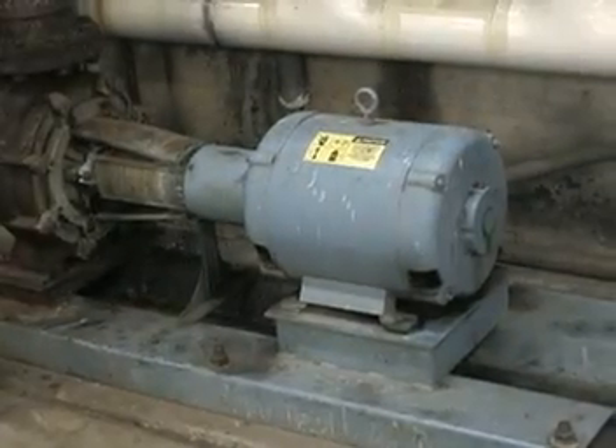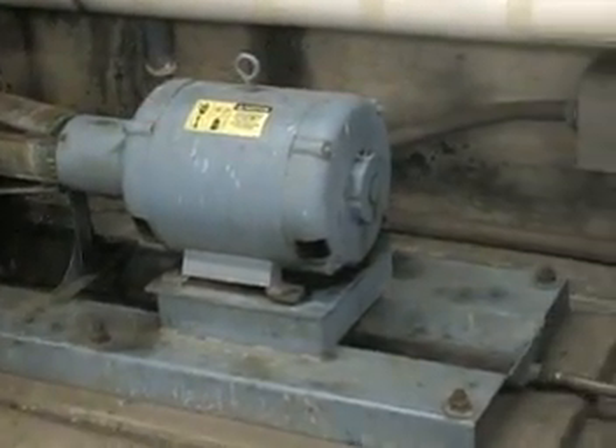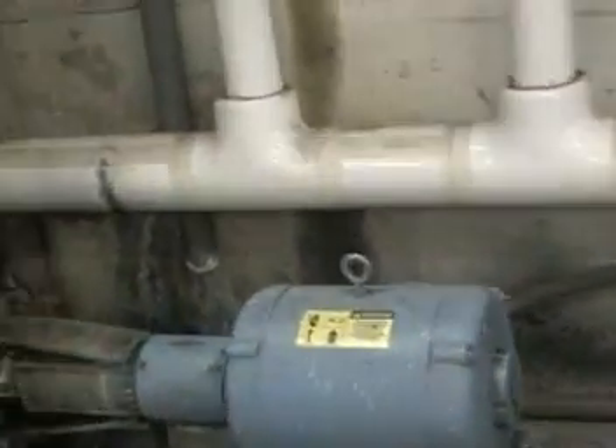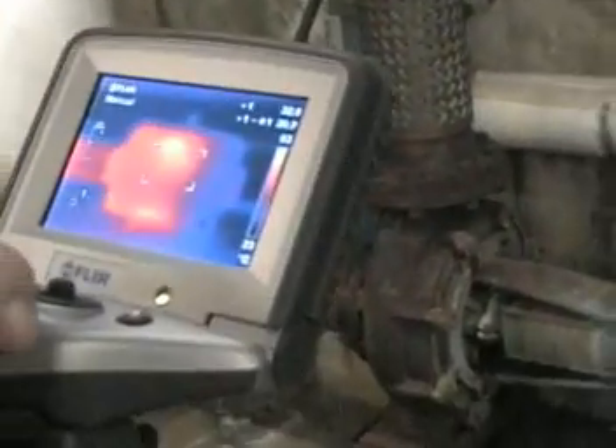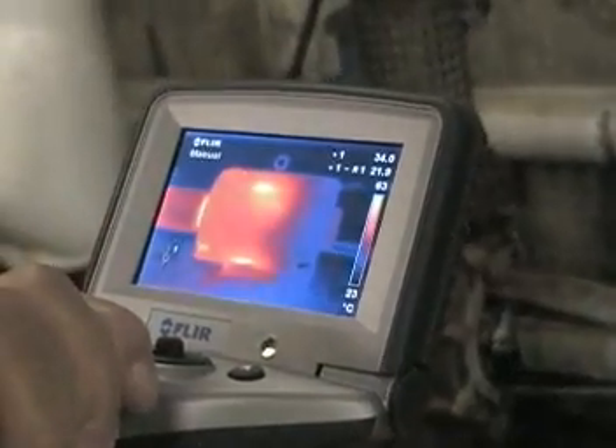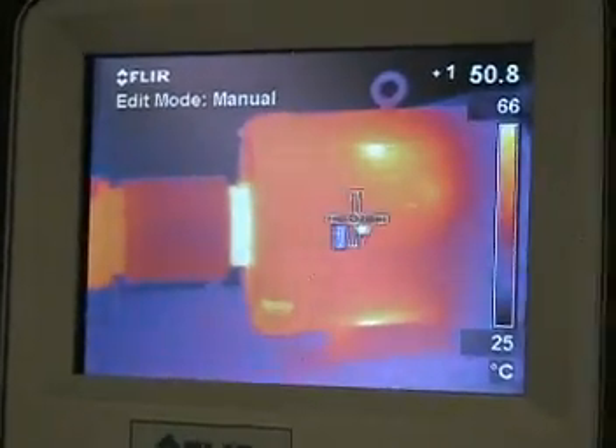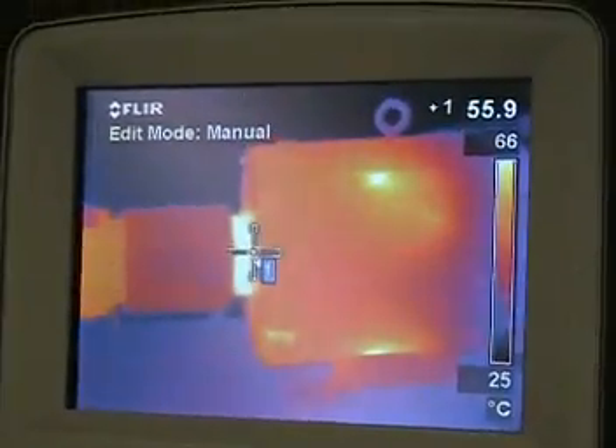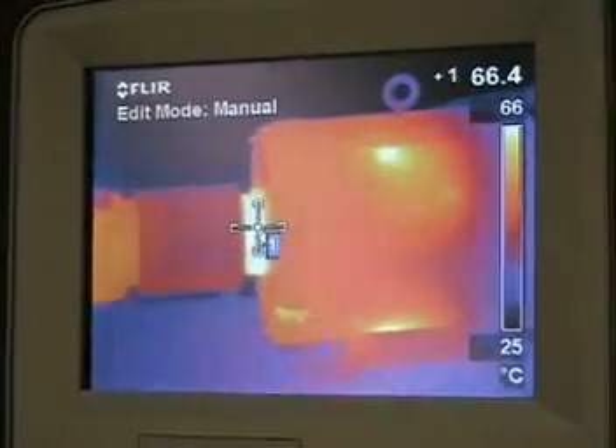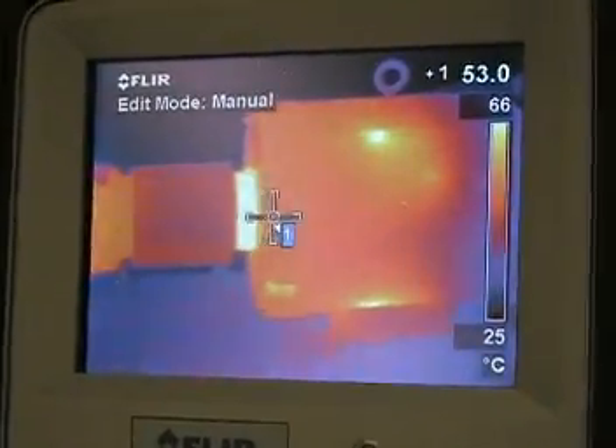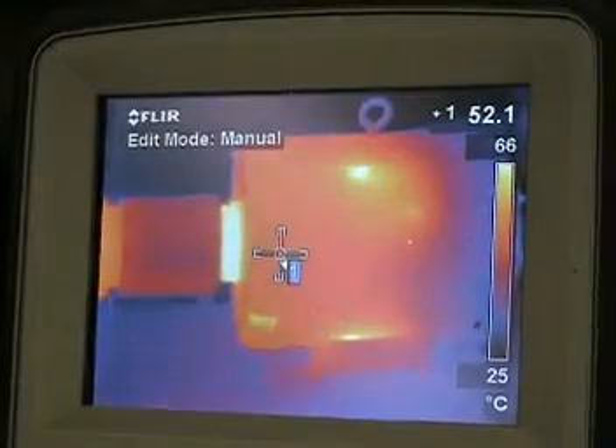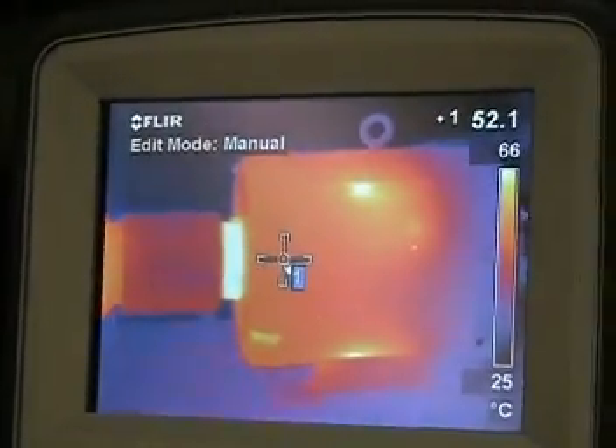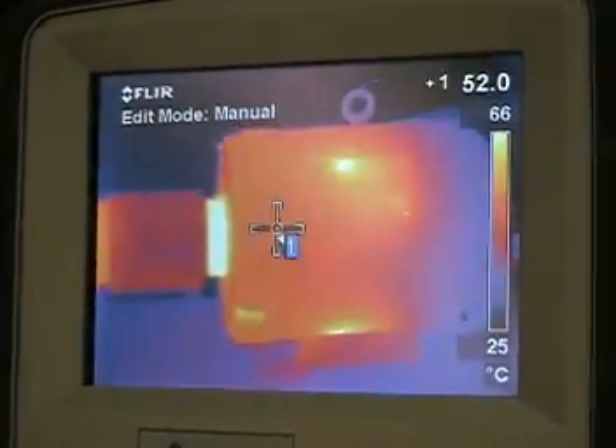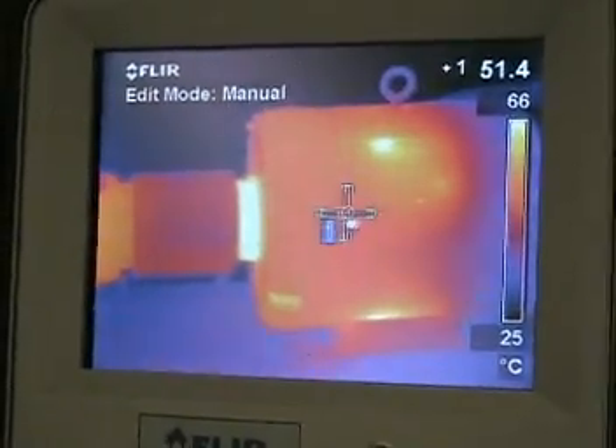What you're about to see is a motor analysis utilizing the infrared camera and the ultrasonic probe. We target the casing of the motor and identify 52 degrees centigrade temperature reading. We use the case temperature as a benchmark to compare the bearing temperature. An alarm will be signaled if we see a greater than a 10 degrees centigrade difference. Keep in mind that this is an indirect measurement and will be lower than the actual bearing temperature.